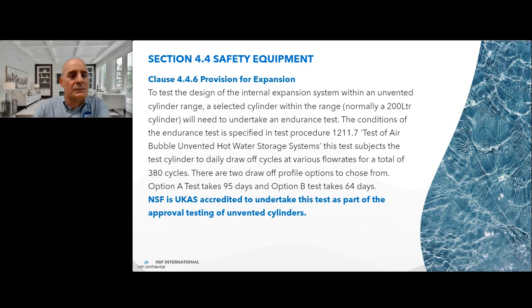So, section 4.4, safety equipment. So 4.4.6, provision of expansion. So to test the design of the internal expansion system within an unvented cylinder range, a selected cylinder within the range, normally a 200-litre cylinder, will need to undertake an endurance test. The conditions of the endurance test is Annex 7, test of air bubble unvented hot water storage systems.